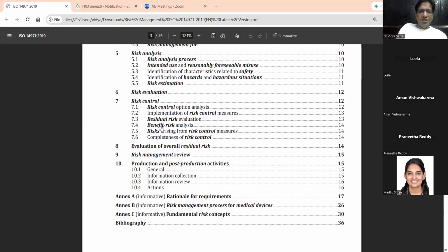We'll do the risk benefit risk analysis. Okay, and the interesting point is risks arising from risk control measures. Are your risk control measures causing new risks? This basically happens not in all, like in production and post-production controls or in IFU and others, but risk controls are mainly focused on the design stages.